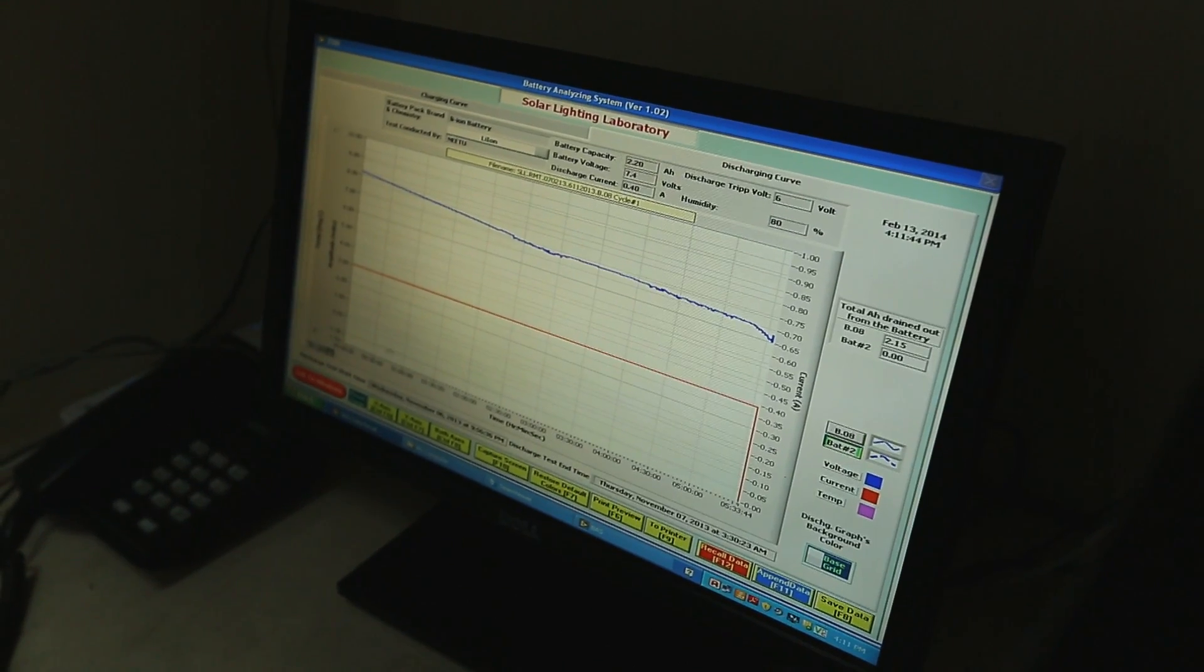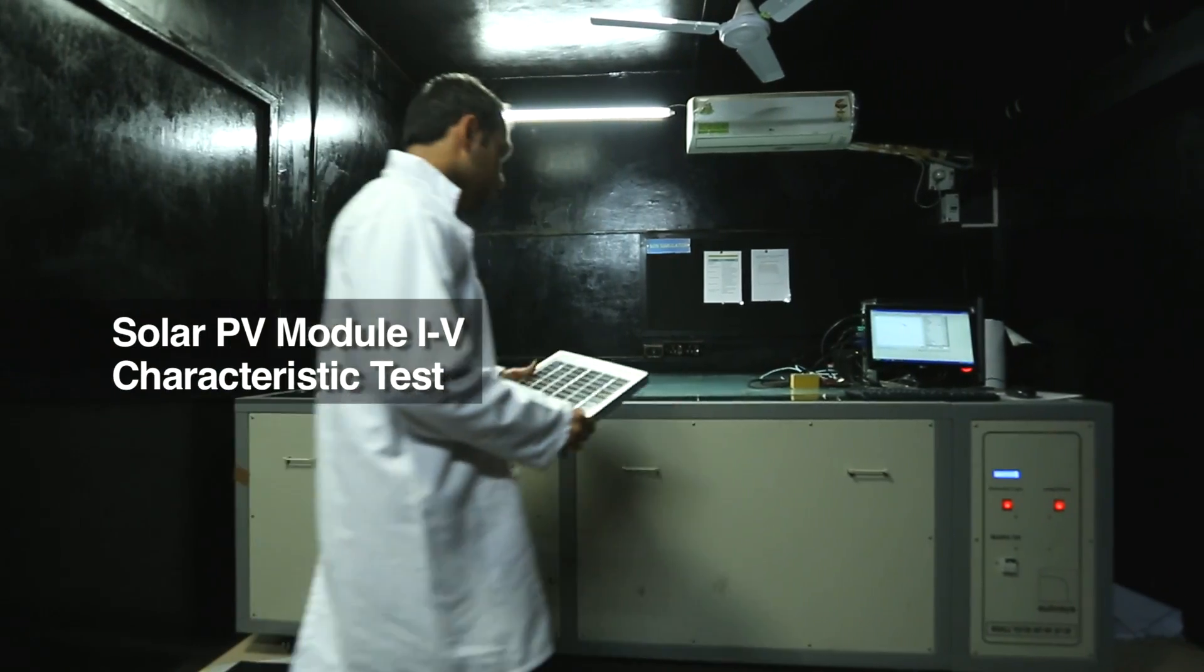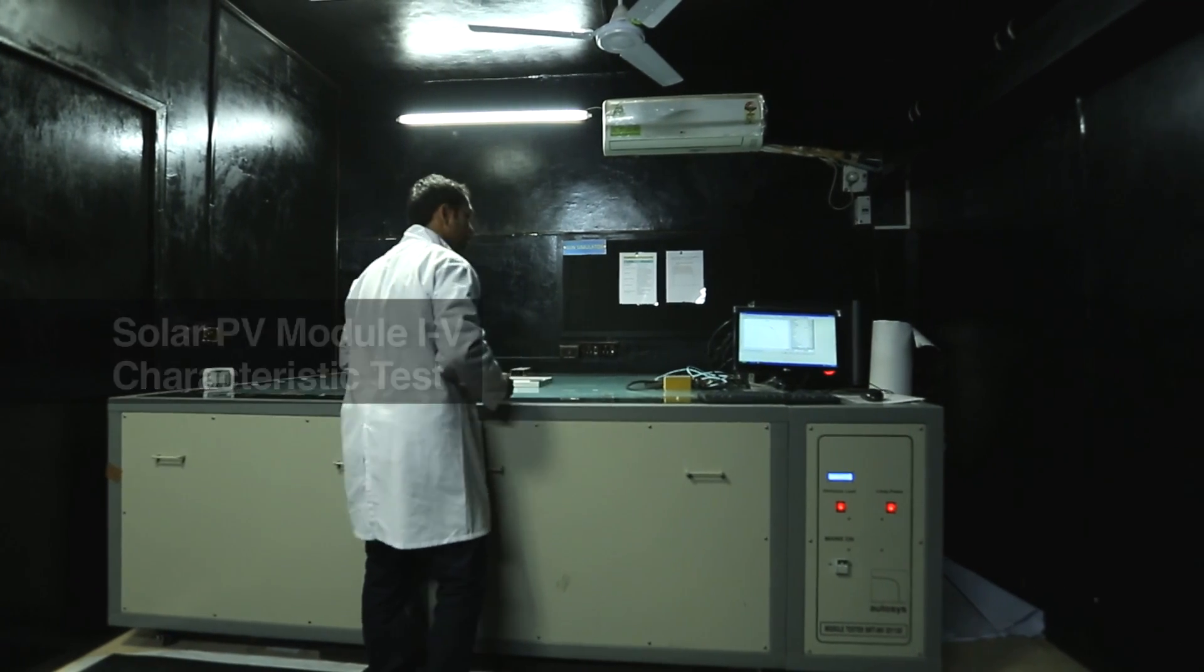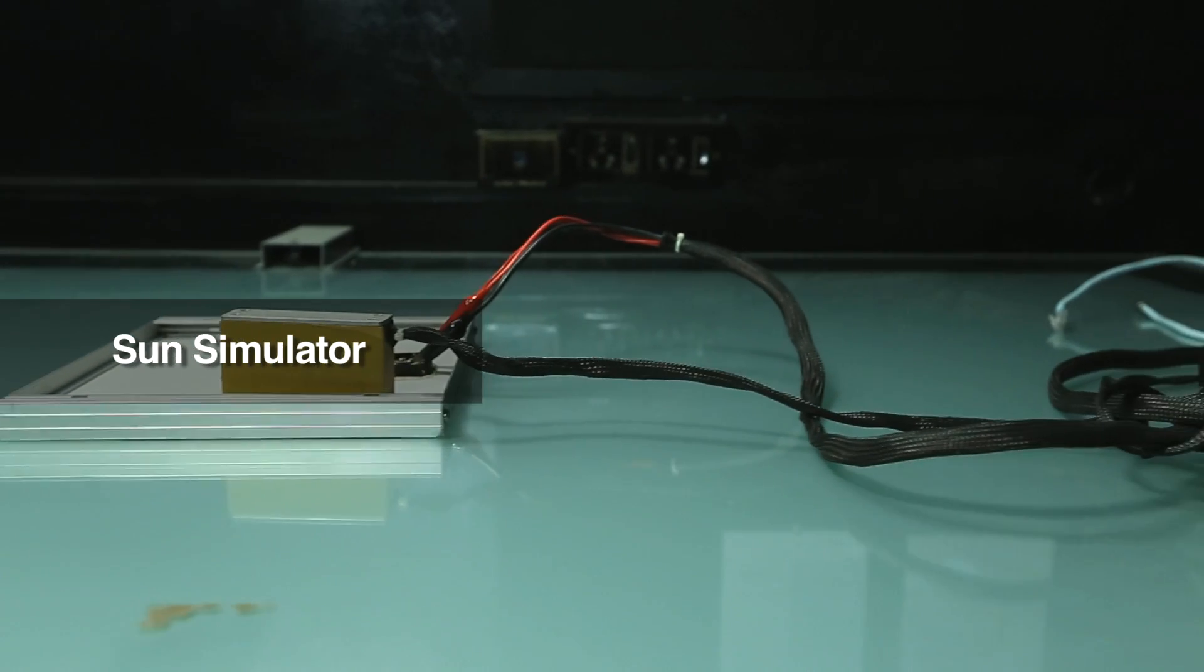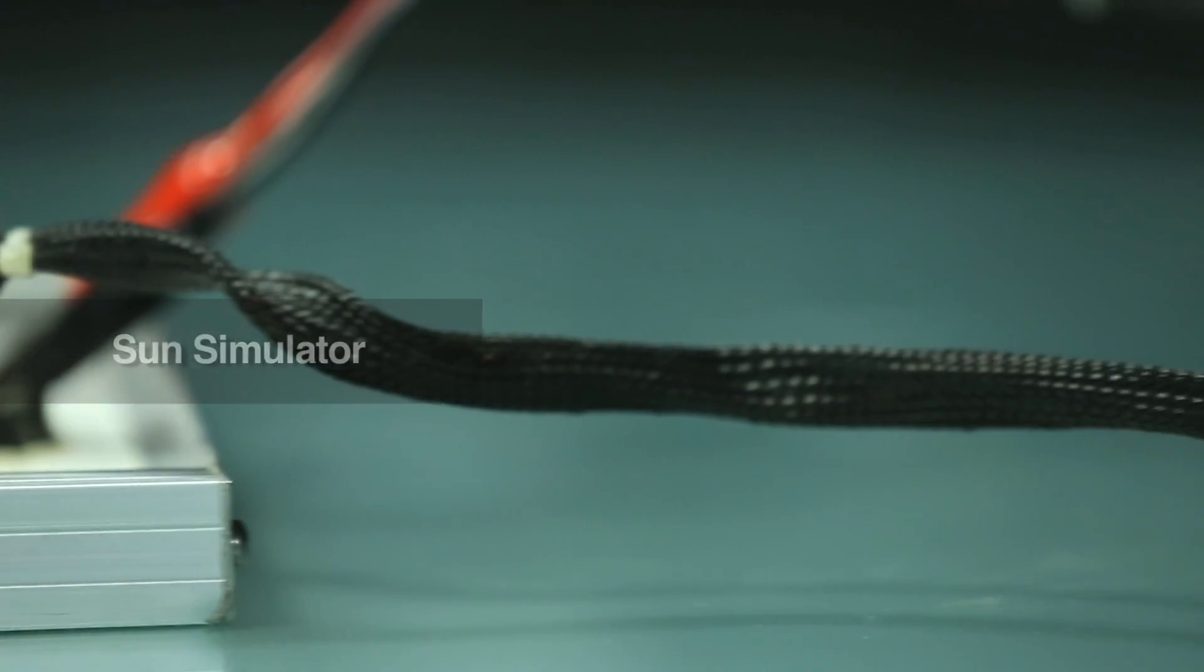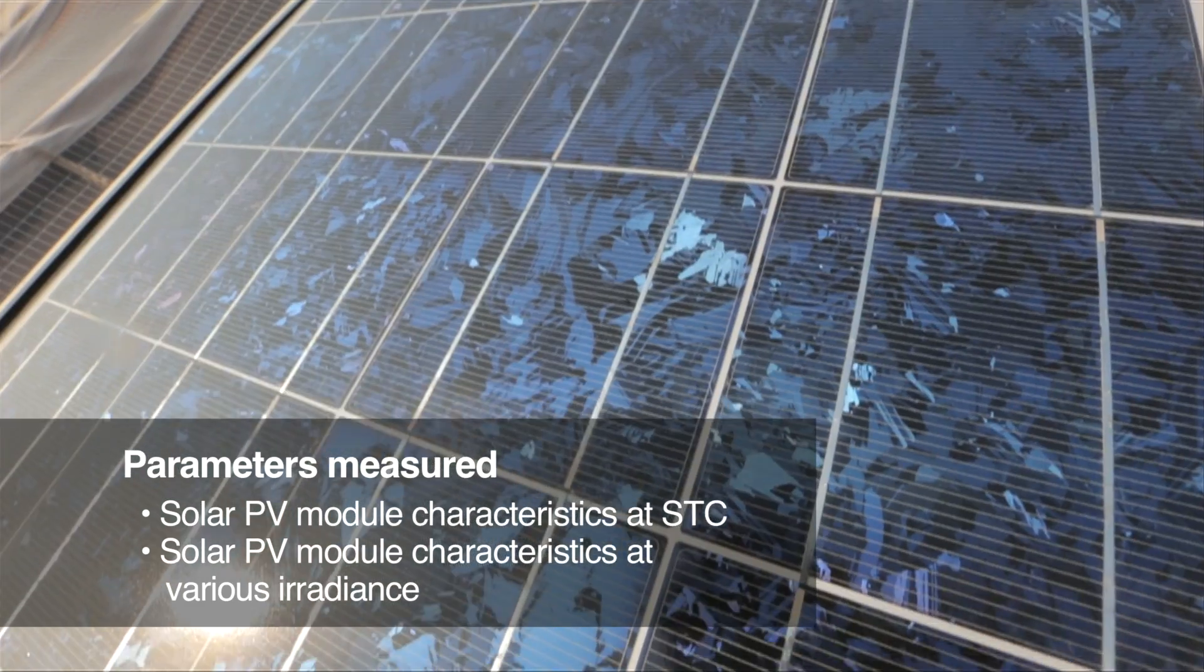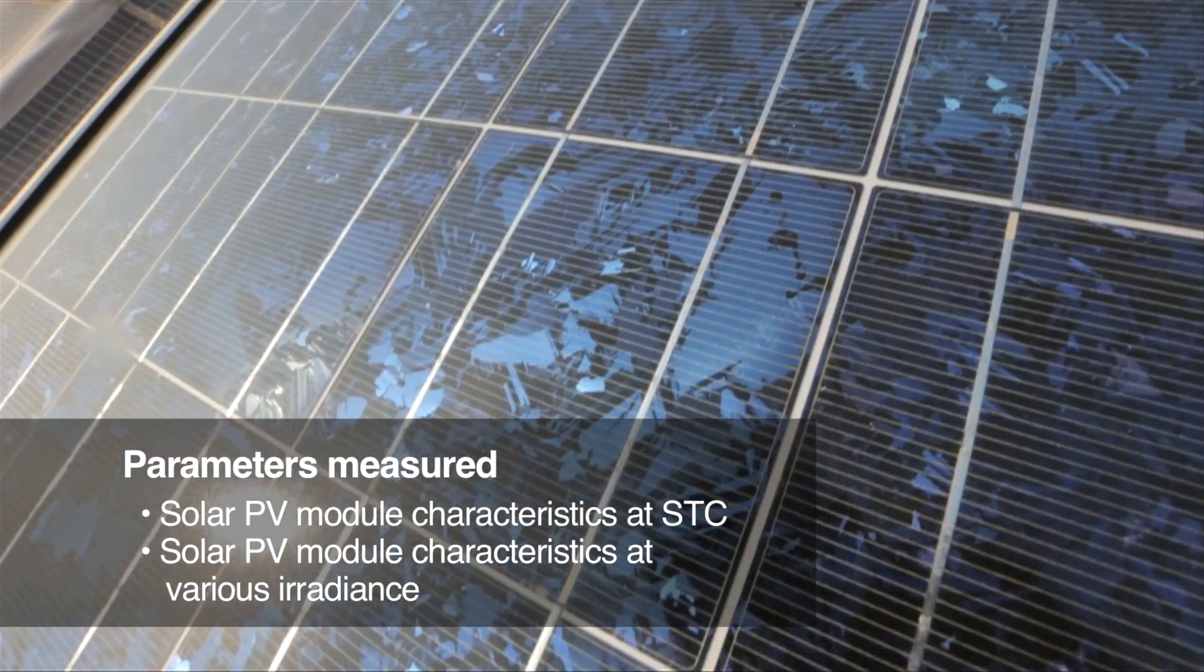In addition to this, the laboratory also has the facility to test photovoltaic module IV characteristics under standard test conditions by using a sun simulator. But beyond testing under controlled conditions, the true performance of a solar module is observed in the outdoors.